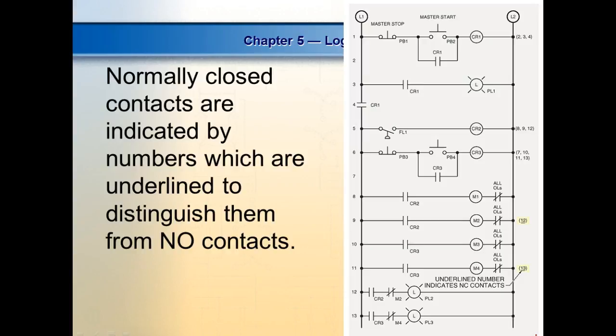So a contactor and a motor starter are going to have contacts in the power circuit. A control relay, the contacts are never going to be in the power circuit, they're going to stay in the control circuit. Everybody understand that?